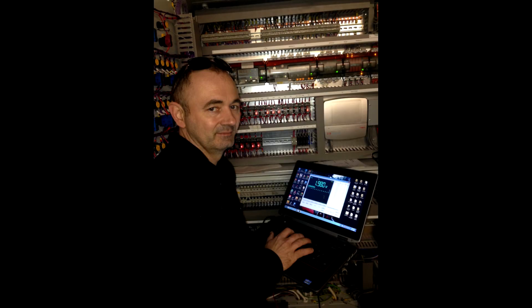Now you only have to take out your tools, your laptop, whatever, and do an investigation. And the investigation will split in two. You will check why the pump is not running. It could be a short circuit, or an earth leak, or mechanical damage. It can be anything. But also you have to investigate the control philosophy, and then you'll find the truth.